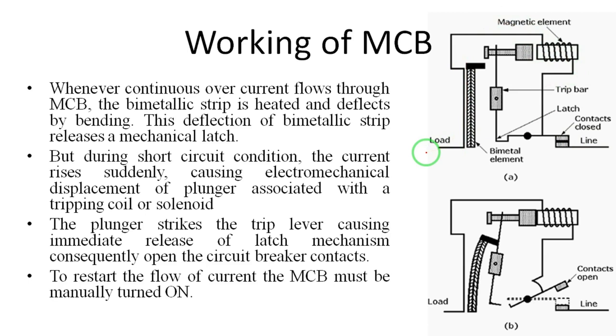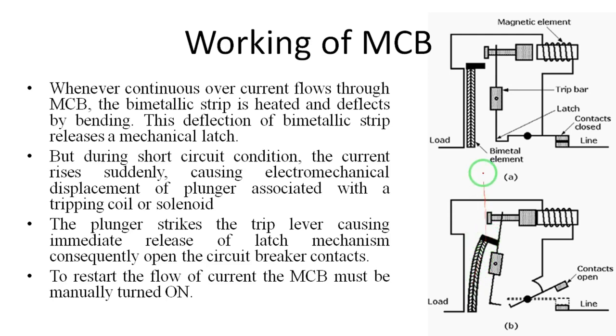Now coming to the main operation: whenever overcurrent flows through the line, the bimetallic element — the bimetallic strip — gets heated and then deflects by bending. When it is heated, the bimetallic strip bends.